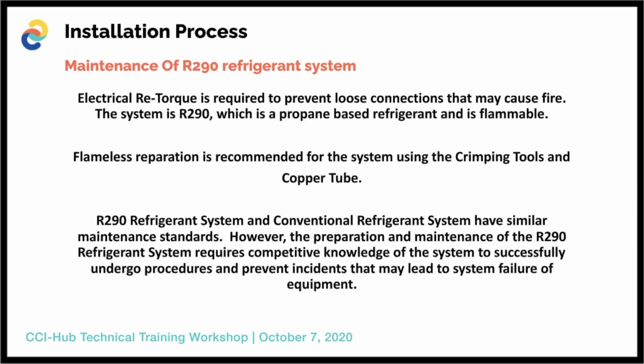Electrical retorque is required to prevent loose connections that may cause fire. The system is R290, which is a propane-based refrigerant, and it's flammable. Flameless repair is recommended for the system, using crimping tools and copper tube. We already bought crimping tools intended for this repair for future problems in the stores. So the clients are confident that the repair only uses crimping tools and no oxyacetylene in the repair of the R290 refrigerant system.